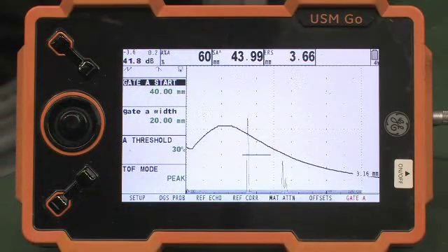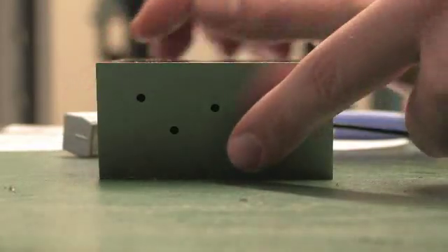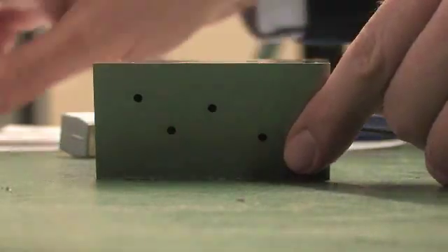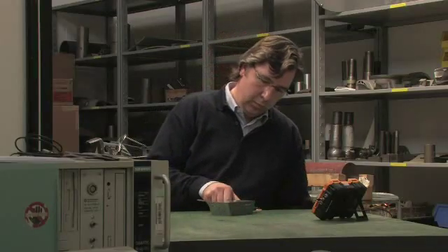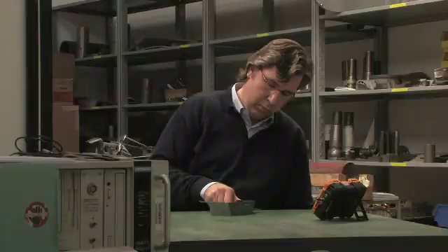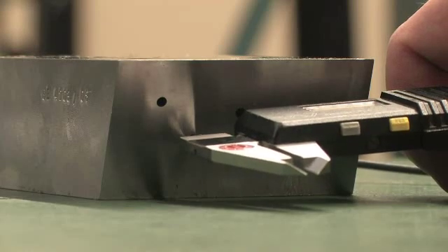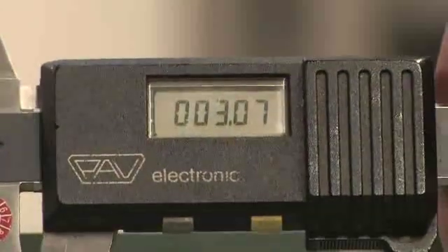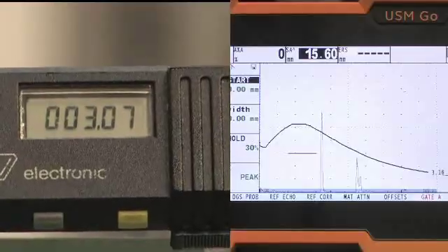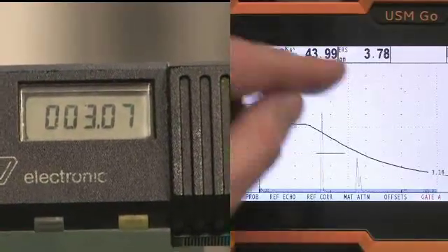We next want to explain an issue discovered in the legacy DGS probes and technique. If I measure the actual diameter of the reflector in this part, you will see that there is a deviation between the measured and the evaluated ERS diameter. This deviation, which is most prominent around the near field endpoint, comes from the fact that legacy angle beam probes normally have rectangular transducer elements that produce sound fields creating this error. Fortunately, tests have indicated that the error results in oversizing indications, and the results were conservative and did not lead to any safety issues.